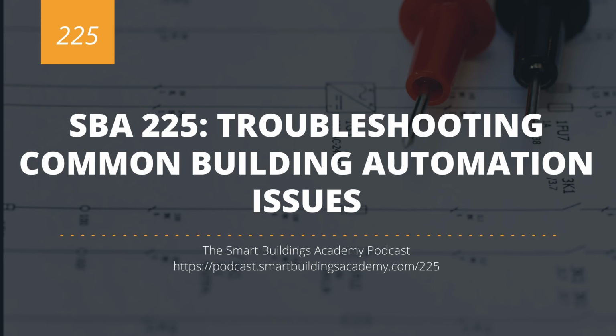most people don't. And so we're finding ourselves showing up on a site and we can ping between our devices because the ping is allowed, but we're not able to have our protocols communicate between devices. And thus we think there's an issue with the server when in actuality, there's an issue with the network. So you can kind of see how that issue is masquerading. And to logically think through that, right, we would say, okay, we have a server and we have supervisory devices. They can't communicate between one another. Is it the server? The quickest way to rule that out is to add your laptop to the network and see if your laptop can communicate to the supervisory devices. If it can, then it's most likely a firewall at the server. If it can't, then it is most likely access control lists at the network.